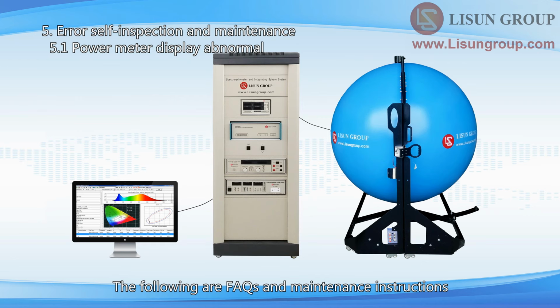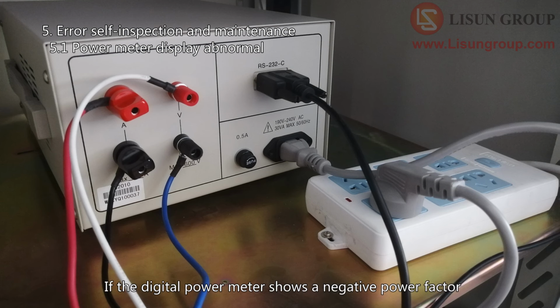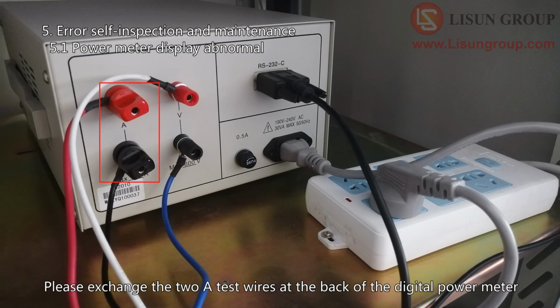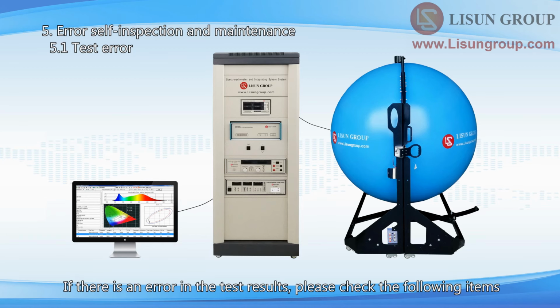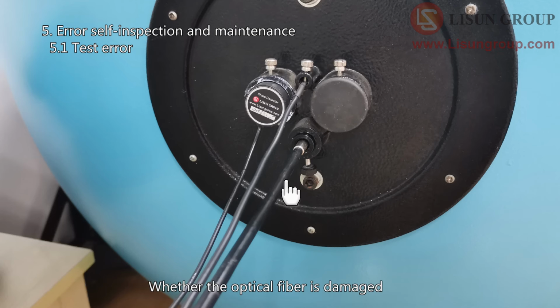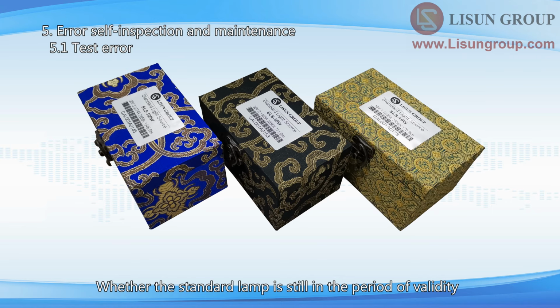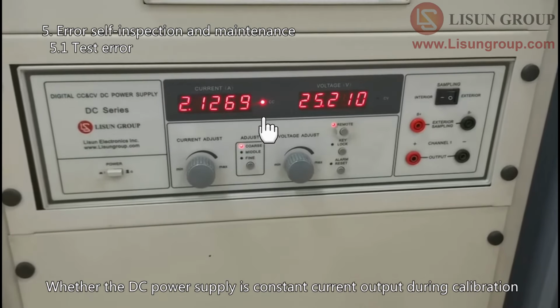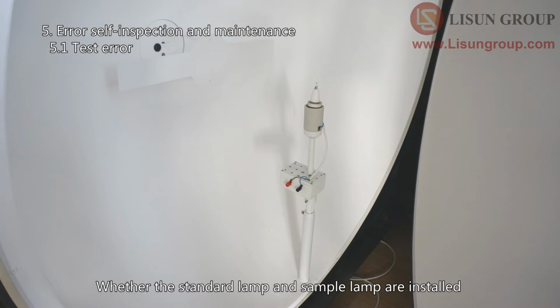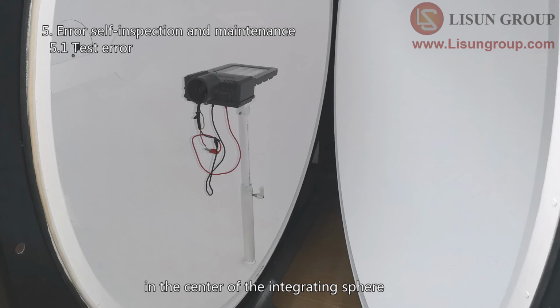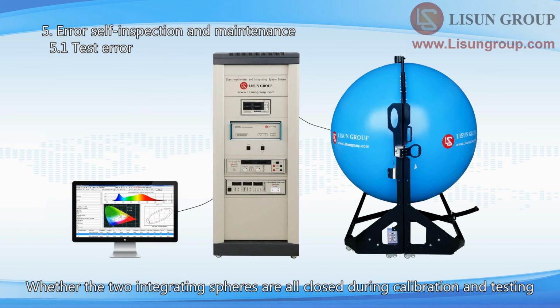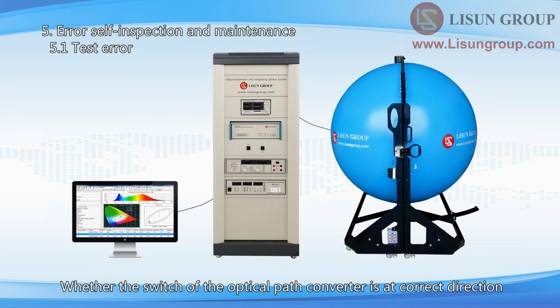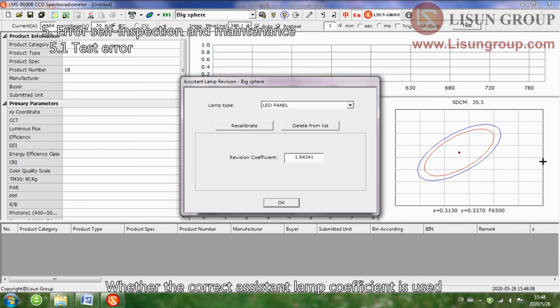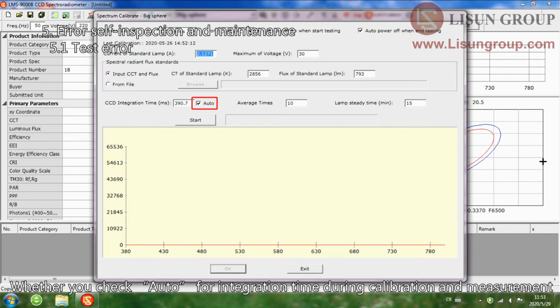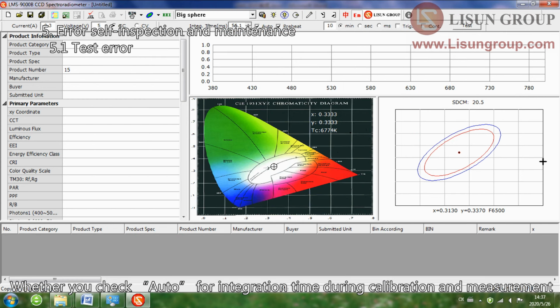The following are FAQs and maintenance instructions. If the digital power meter shows a negative power factor, please exchange the 2A test wires at the back of the digital power meter. If there is an error in the test results, please check the following items: whether the optical fiber is damaged, whether the standard lamp is still in the period of validity, whether the DC power supply is constant current output during calibration, whether the standard lamp and sample lamp are installed in the center of the integrating sphere, whether the two integrating spheres are all closed during calibration and testing, whether the switch of the optical path converter is at the correct direction, whether the correct assistant lamp coefficient is used, and whether you check auto for integration time during calibration and measurement.